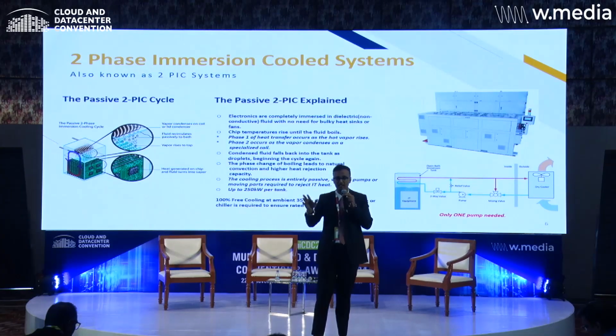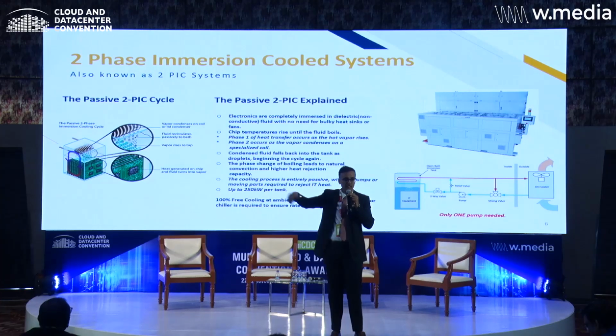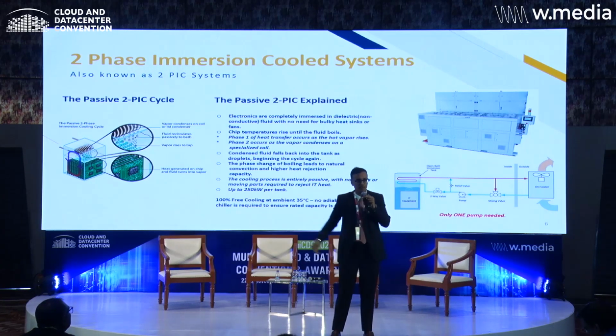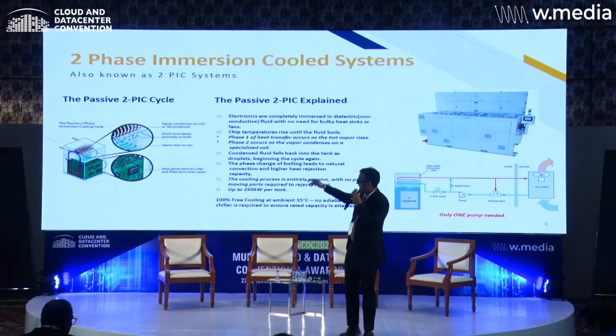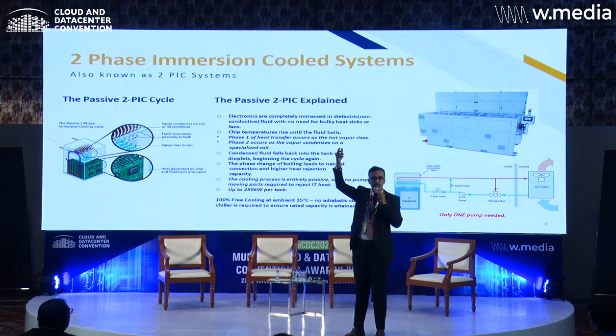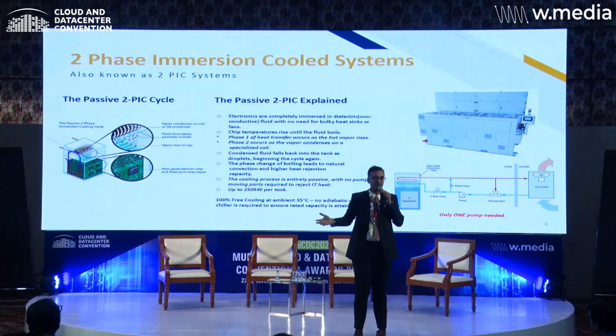When it turns into vapor, you have a small copper coil running over the vapor, which is transporting ambient temperature water. Nothing more than ambient temperature, nothing less. So you don't require chillers, you don't require CRAC units, you don't require PAHUs, nothing. You just have a dry cooler outside which is doing free cooling and transporting water at 40 degrees or 38 degrees. The vapor will interact with the coil and convert back into liquid, like normal convection, and then fall into the tank again.